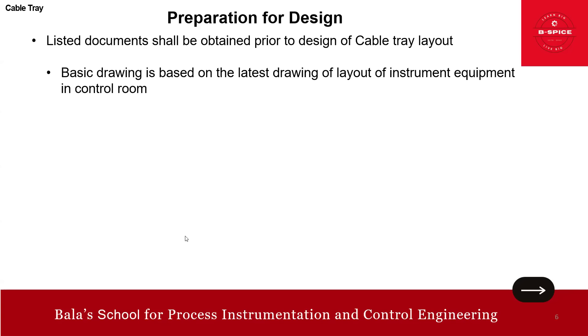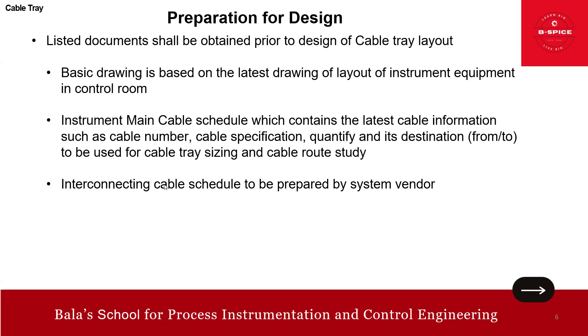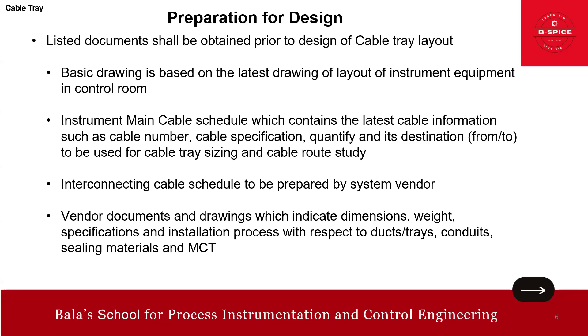For preparatory activities: we need the latest instrument equipment layout in the control room showing all the panels. We also need the instrument main cable schedule, which contains the latest cable information such as cable number, cable specification, and quantity - used for cable tray sizing and cable route study. Then interconnecting cable documents prepared by the system vendor, and vendor documents indicating dimension, weight specification, and installation details with respect to ducts, trays, conduits, sealing materials, and MCT.